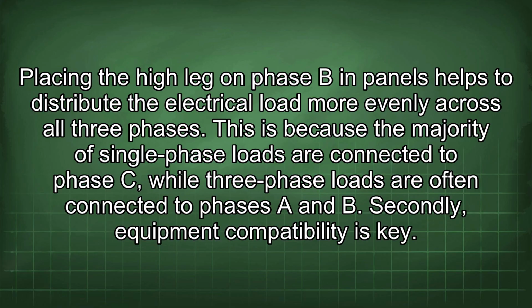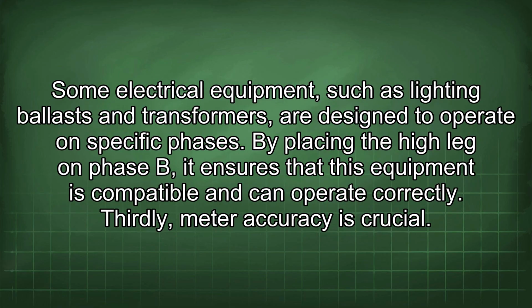Secondly, equipment compatibility is key. Some electrical equipment, such as lighting ballasts and transformers, are designed to operate on specific phases. By placing the high leg on phase B, it ensures that this equipment is compatible and can operate correctly.